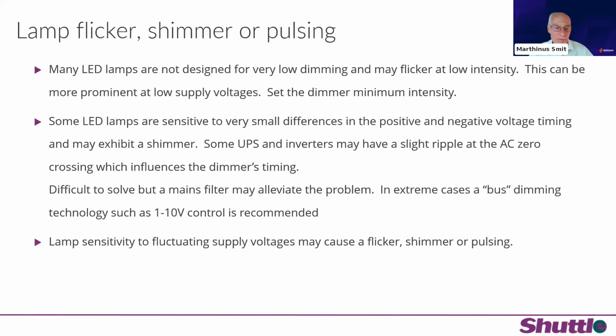In those cases, we recommend that the client experiment with different lamps. Typically, the lamps from your traditional European suppliers or European brands have much more of what we call capacitance in the lamp, and they are more robust against these fluctuations than some of the later lamps, which are very sensitive. So experiment with different LED models. A mains filter may solve the problem, and the jury is still out on that one. Sometimes it works, sometimes it doesn't. And then in extreme cases, especially in restaurant environments, the best option is to change to a bus technology such as 1 to 10 volt control, which is very much immune to any such problems.